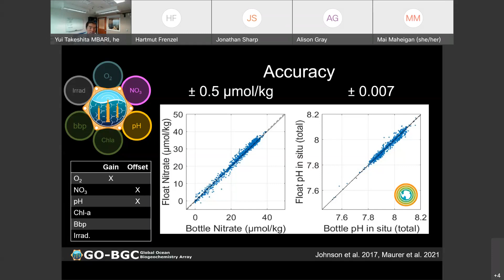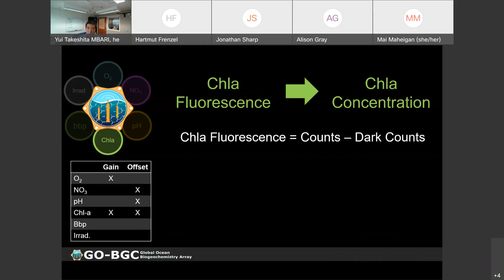Okay, moving on to chlorophyll A fluorescence. The sensor measures fluorescence and we convert it to chlorophyll A concentration, because that's what we are interested in. In order to do that, there are basically two corrections. One is the bias correction, or the offset, where we account for the dark counts, and we do that by looking at the deep data.